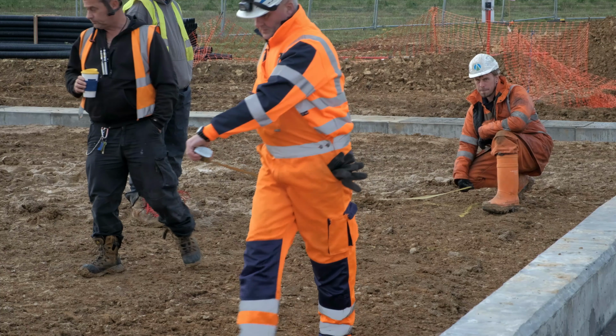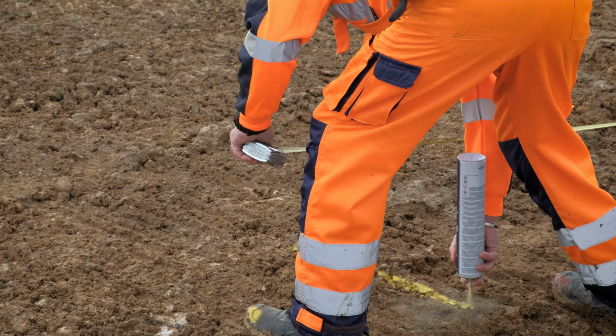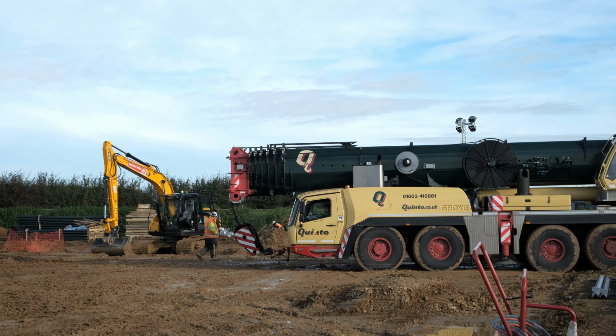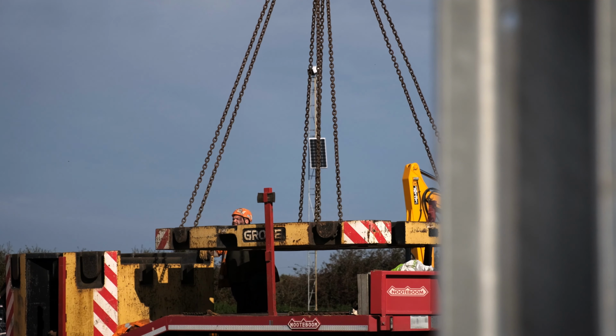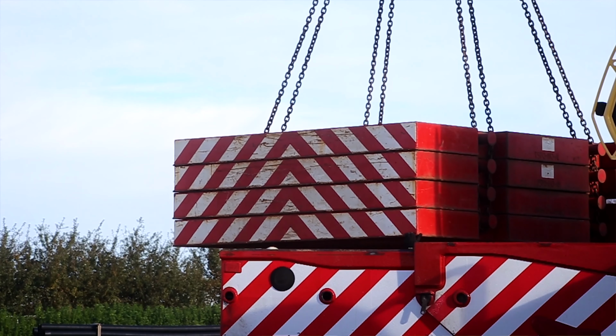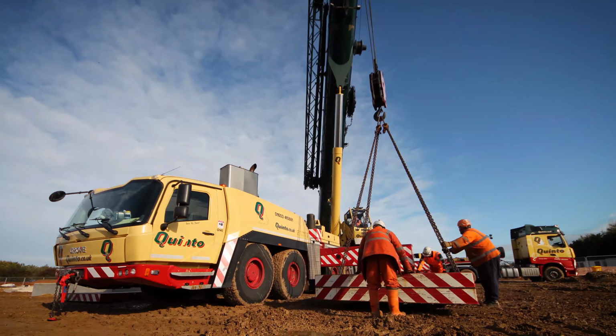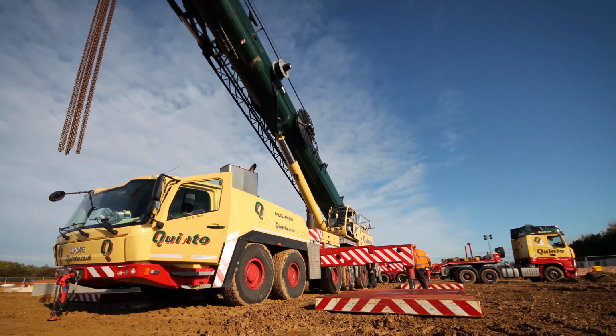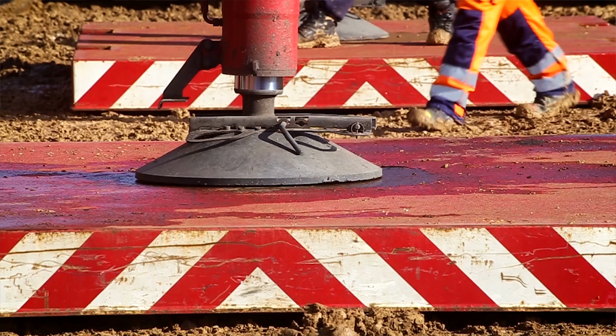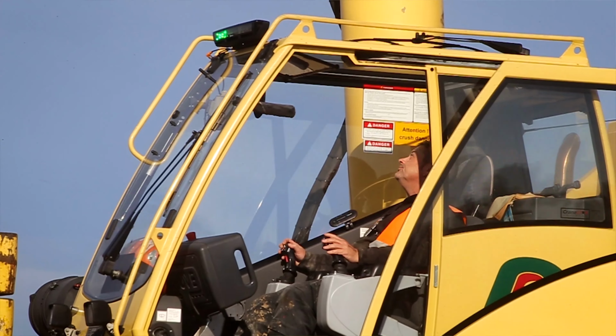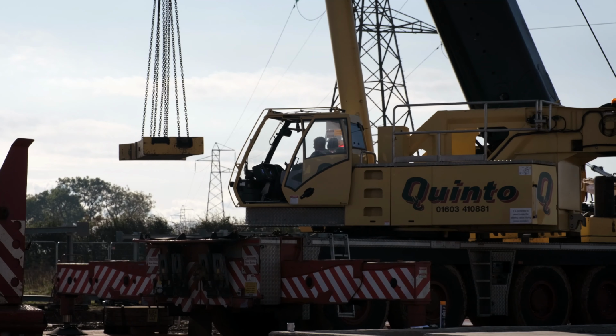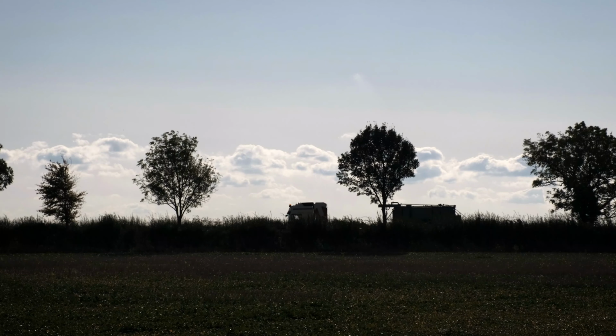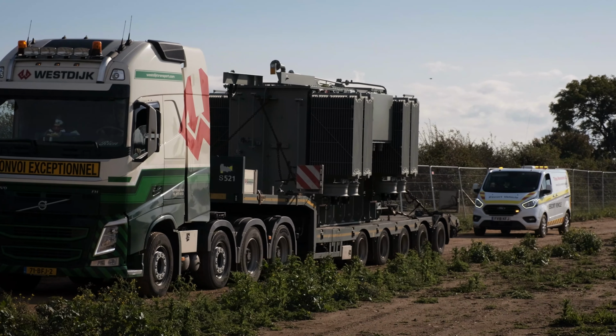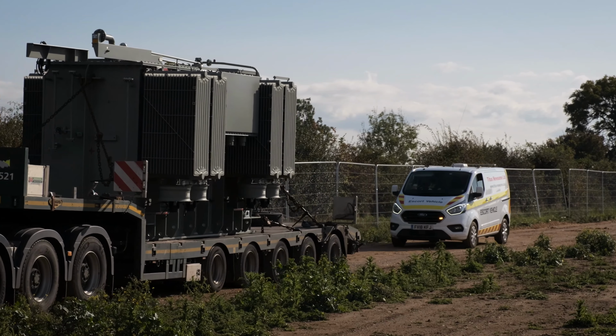Installing a transformer is a long process. Firstly, you've got to build the transformer, then deliver it to site, place it on the plinth, as can be seen behind me. Then we put together the final pieces, the conservator, the bushings. Once that's in place, we top up the oil, test the oil to make sure it's right, and send a sample to the lab just to be sure. Then we do some electrical tests, connect all the auxiliary equipment onto the transformer, connect the auxiliary equipment to the substation, test everything again, and then test it again just to be sure. And then we start with the HV equipment, connecting it to the overhead lines via the switch gears and disconnectors, and then we switch it on, and it's then in service.